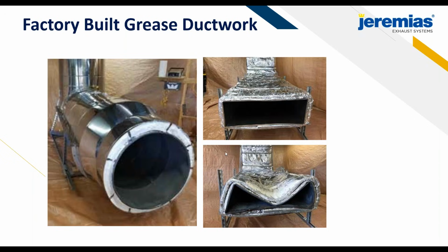One other aspect of this that I like to point out is that with factory-built grease duct, the manufacturer, Jeremias, will also provide all the structural supports as well. And that's key too, because I've seen in my experience a lot of these structural supports aren't the best if the fire gets outside the duct. And once that collapses, the duct just collapses in the space, and now you have a fire in your entire space. So in the end, what this grease duct is designed to do in a fire is keep the fire contained within the grease duct, and that is what factory-built grease duct will excel in.